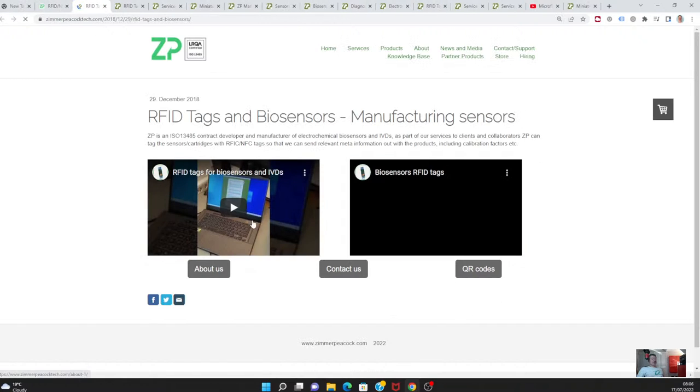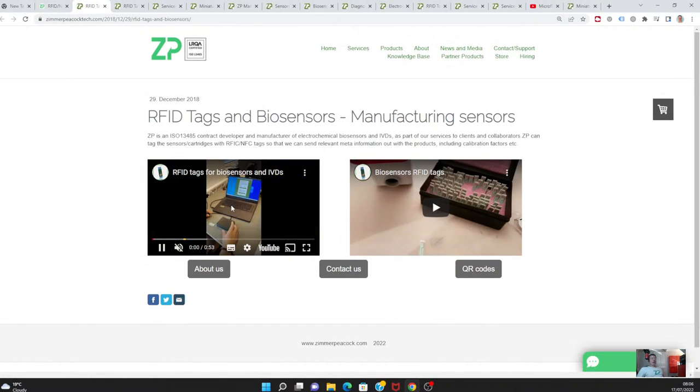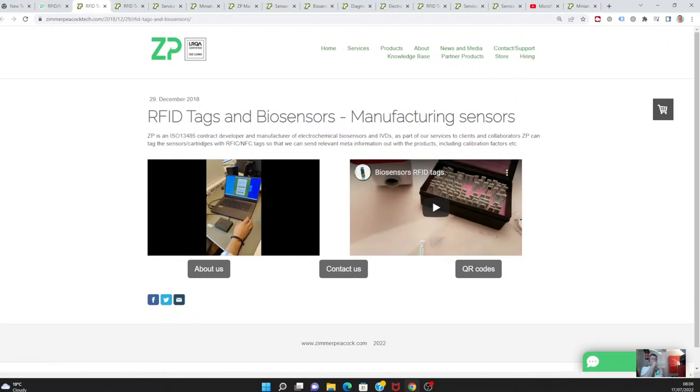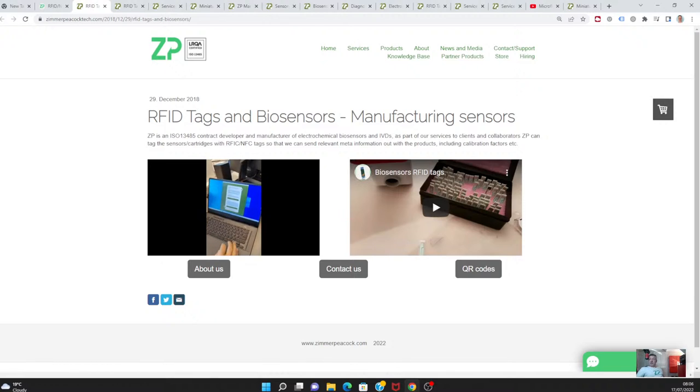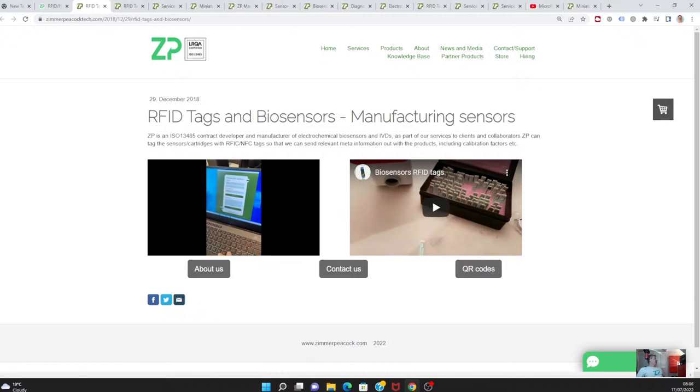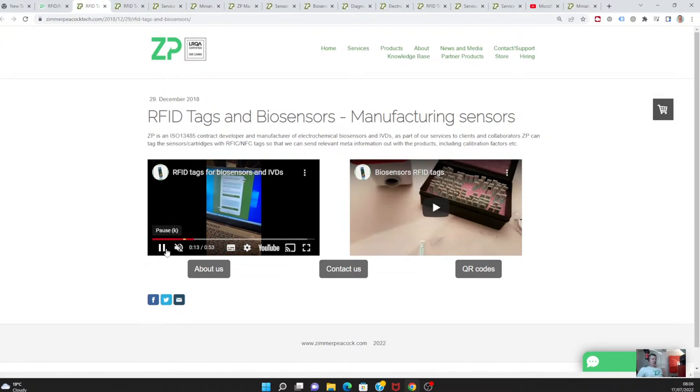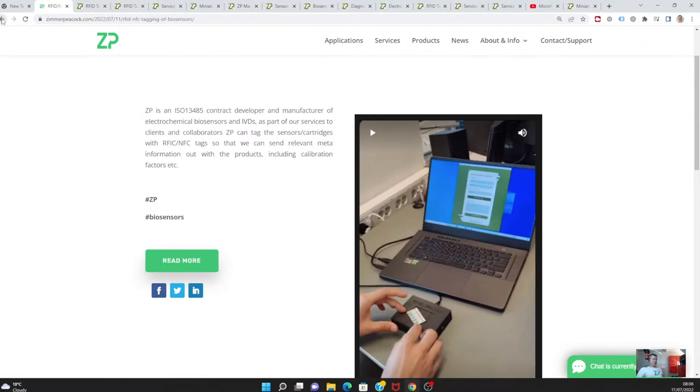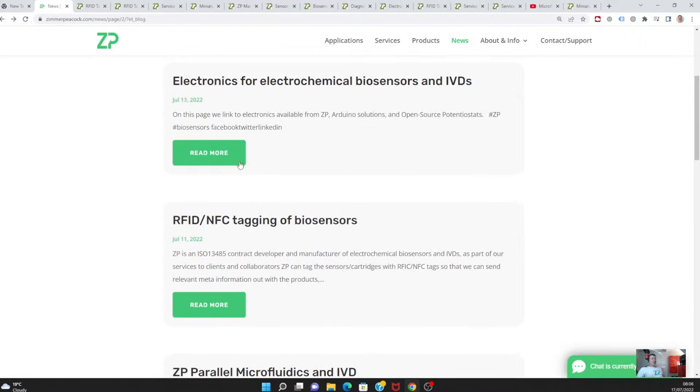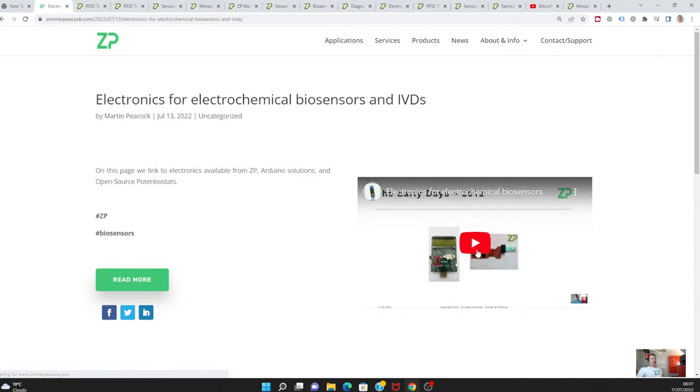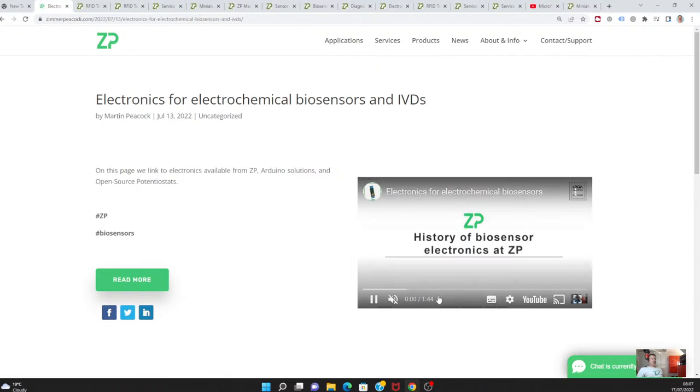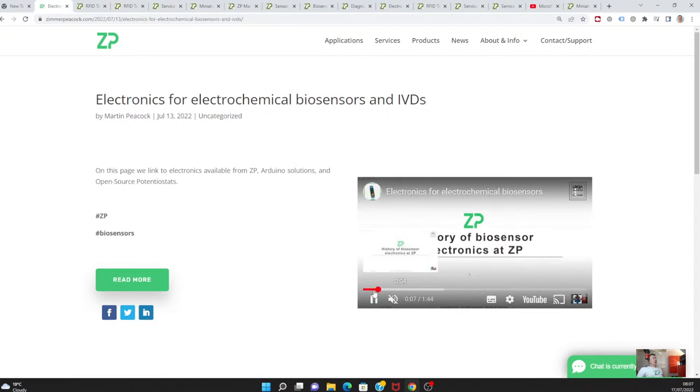With this RFID tagging technology that we have, we're able to capture those variations and actually embed them on a chip and put that chip with the sensor. So the sensor can go out the factory door with calibration built into it. That is definitely something that we can do at Zimmer and Peacock. We also put a little video up this week really talking about the history of electronics at ZP, because Zimmer Peacock Limited has been running for eight years.